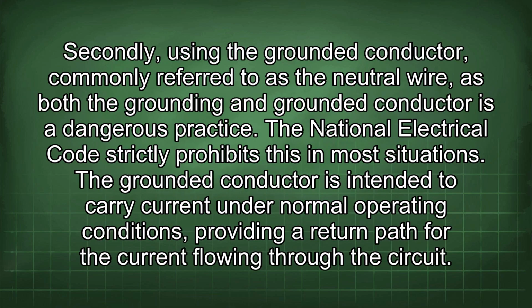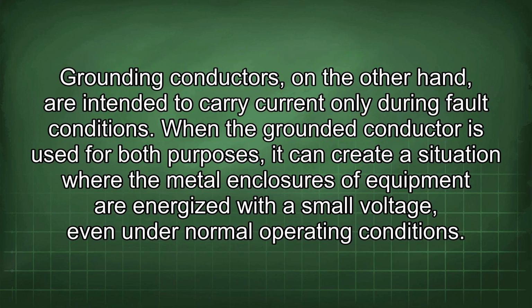Secondly, using the grounded conductor, commonly referred to as the neutral wire, as both the grounding and grounded conductor is a dangerous practice. The National Electrical Code strictly prohibits this in most situations. The grounded conductor is intended to carry current under normal operating conditions, providing a return path for the current flowing through the circuit. Grounding conductors, on the other hand, are intended to carry current only during fault conditions. When the grounded conductor is used for both purposes, it can create a situation where the metal enclosures of equipment are energized with a small voltage, even under normal operating conditions.